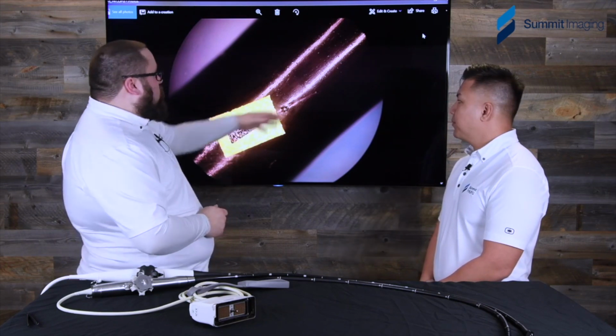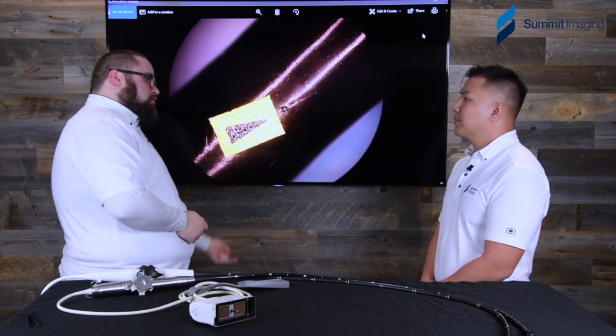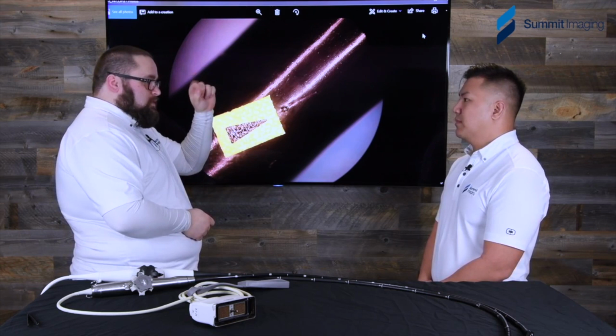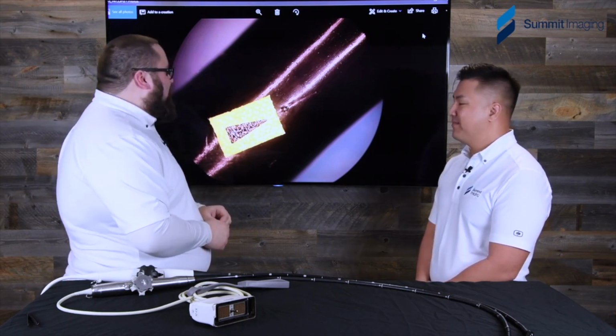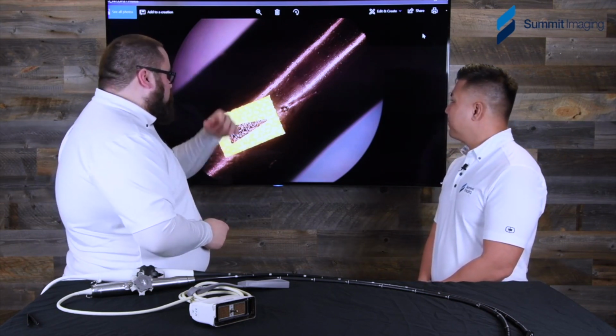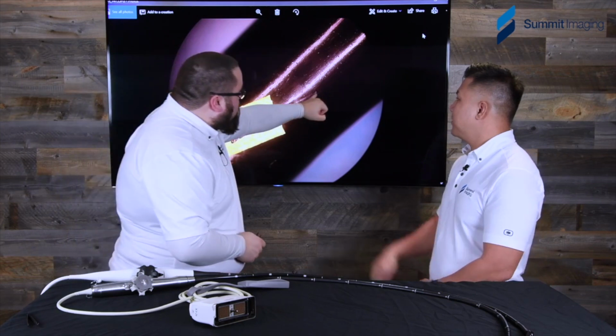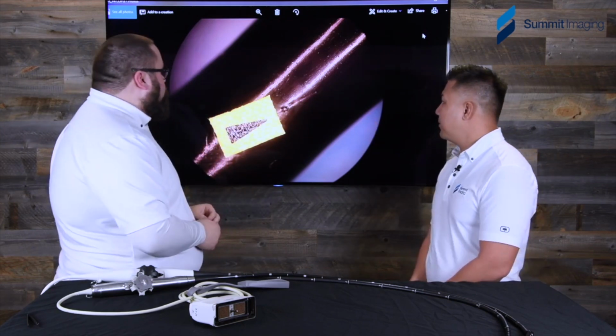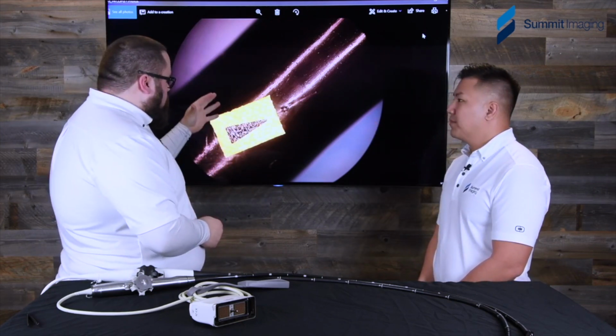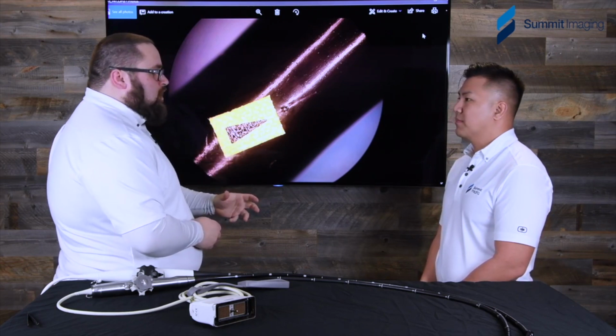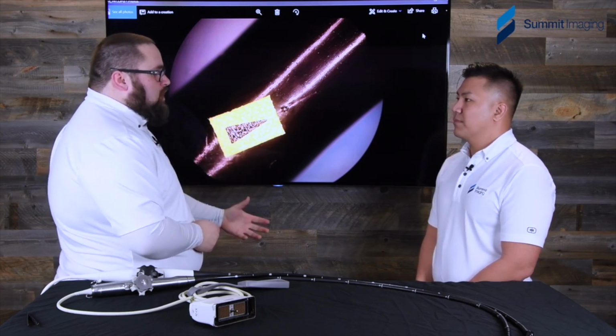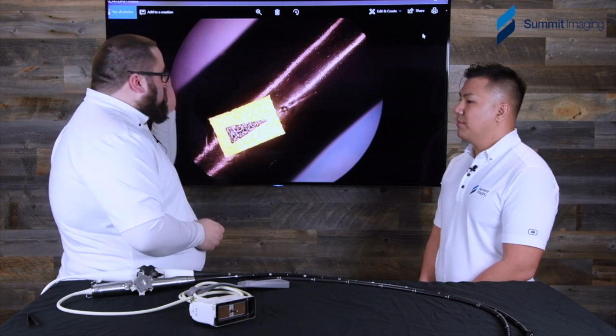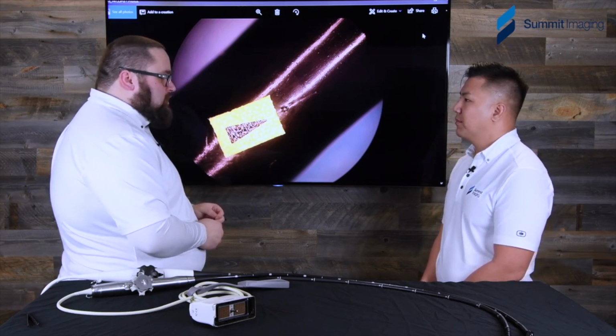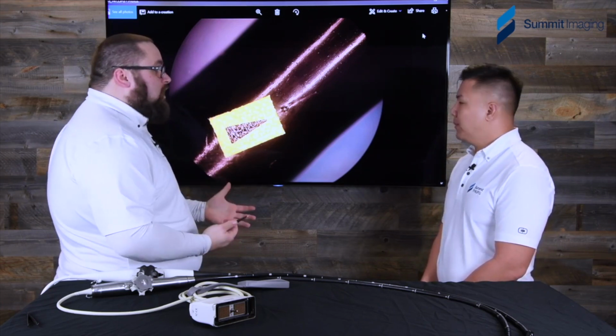Now this is the one that you can see. There's probably going to be one on the other side, because your mouth works in 2 directions. And you may have multiple across the whole piece. In fact, you can see there's another one right here, even smaller. But if we had caught this during the leakage test, during our initial disinfection of this probe, it would have been repaired very quickly, very easily, and there wouldn't be fluid really anywhere.